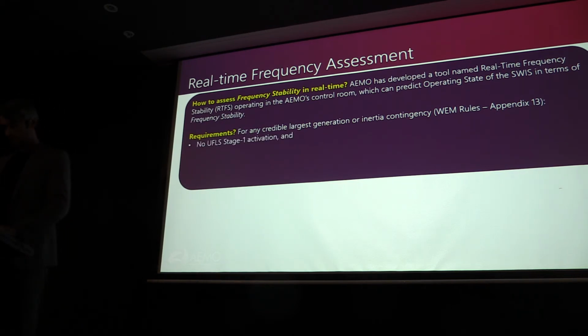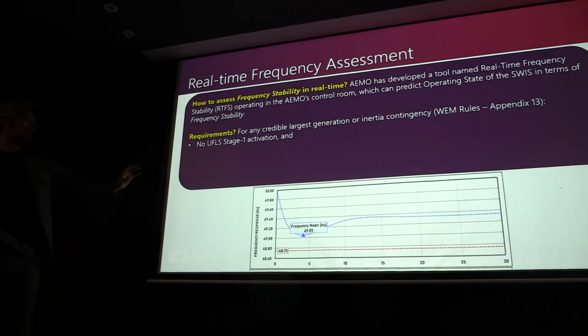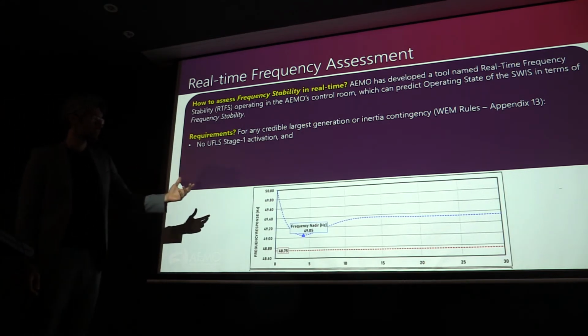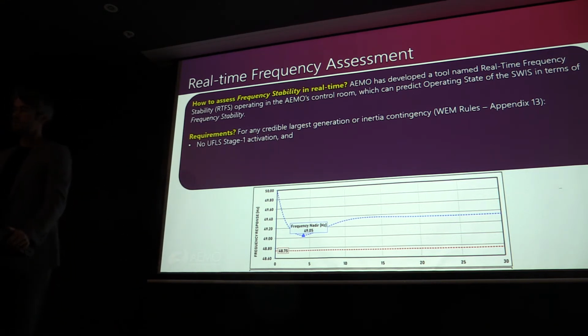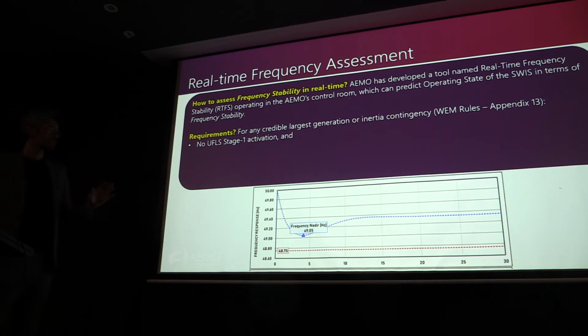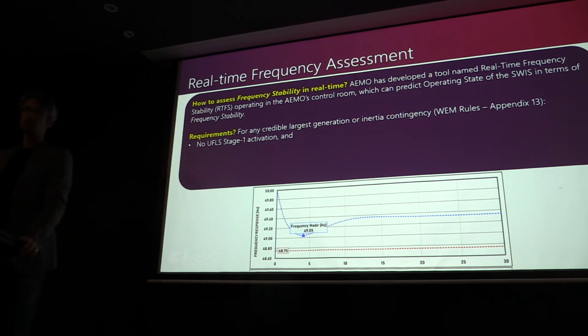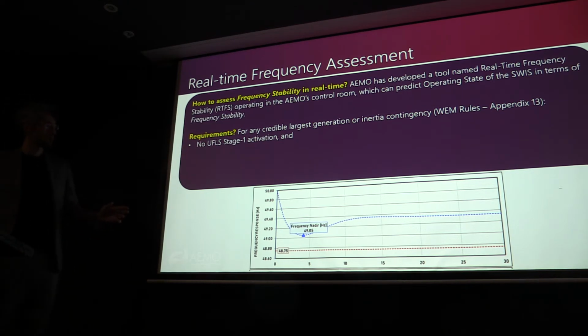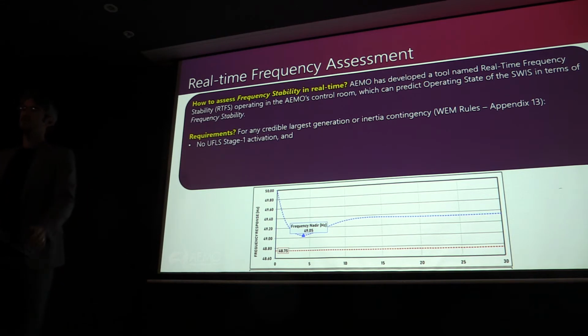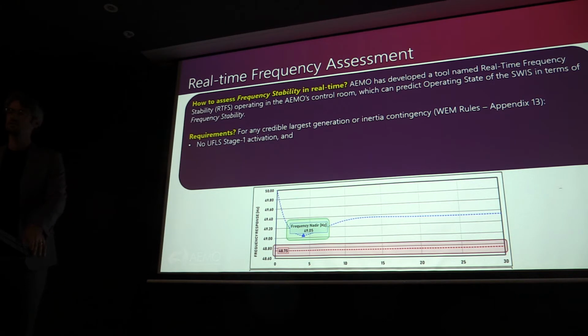So when we say frequency stability, what do we mean? The requirements we consider: this is a trace of a typical frequency after a large contingency generation loss. The aim we're trying to achieve is that we're not supposed to hit stage 1 UFLS. The threshold in the technical rules is 48.75. The minimum point of the frequency trace after generation loss shouldn't touch the UFLS threshold. That's one requirement, the frequency nadir.